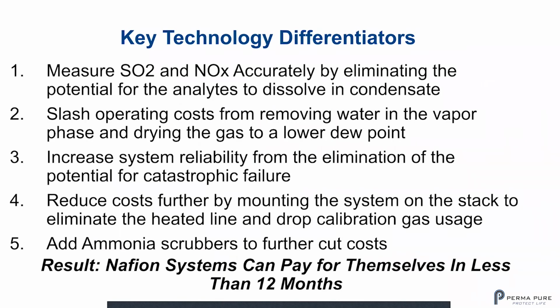So the key technology differentiators with our systems is, number one, we measure SO2 and NOx accurately by eliminating the potential for analytes to dissolve in the condensate. Number two, we slash operating costs from removing water in the vapor phase and drying the gas to a lower dew point. This has many benefits we'll describe later on. We increase system reliability from the elimination of the potential for catastrophic mechanical or electromechanical failure.